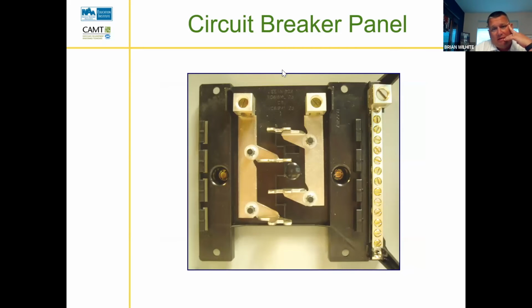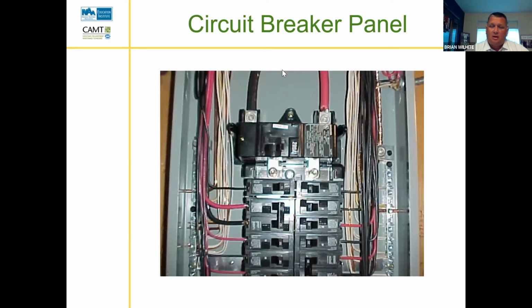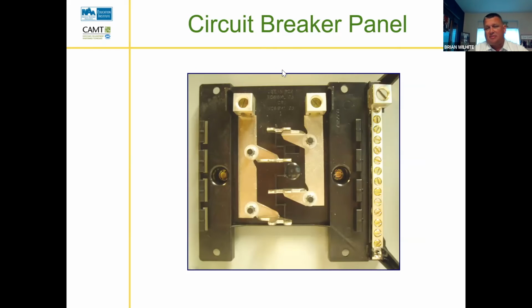Circuit panel. The back of the circuit panel where the breaker hooks up is very brand specific. If we're going to replace a breaker in this panel, and this is a Square D panel, I need to put a Square D breaker back in here. I can't go get a GE breaker or a Siemens breaker. Breakers are very brand specific. So if it's a Square D, it needs a Square D.